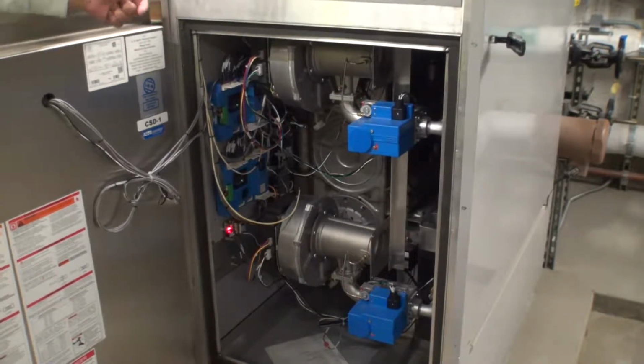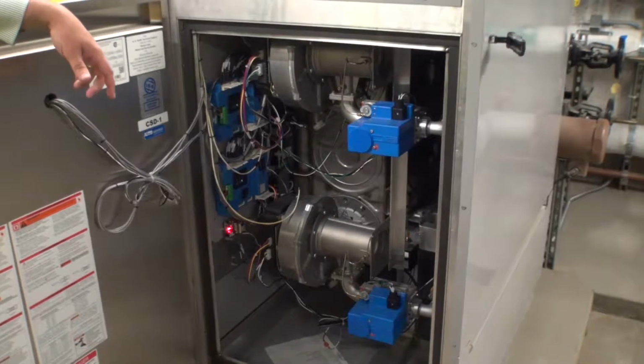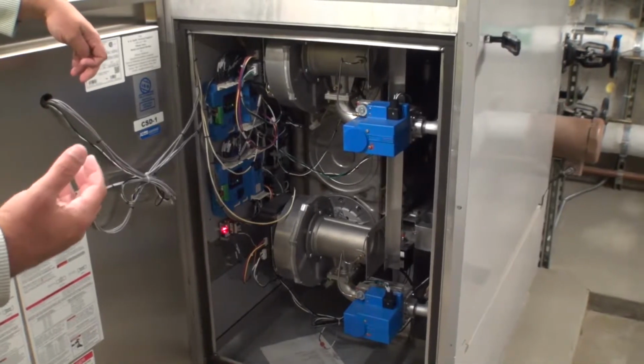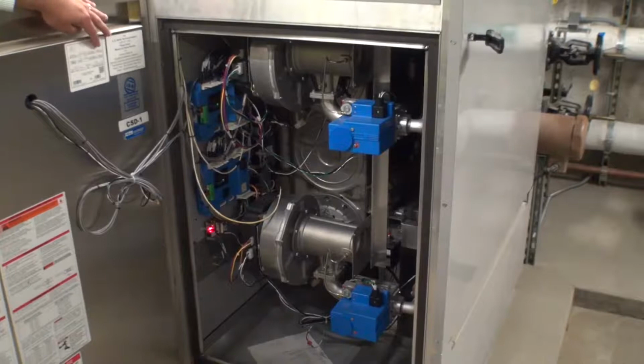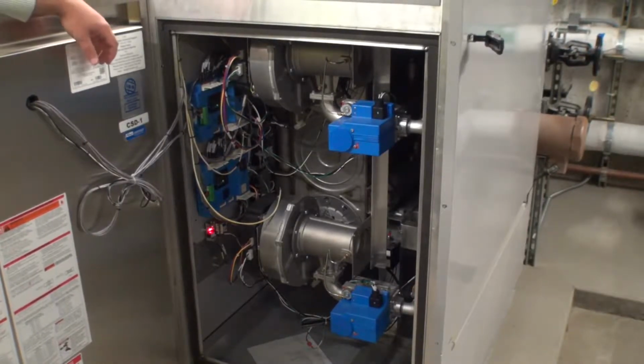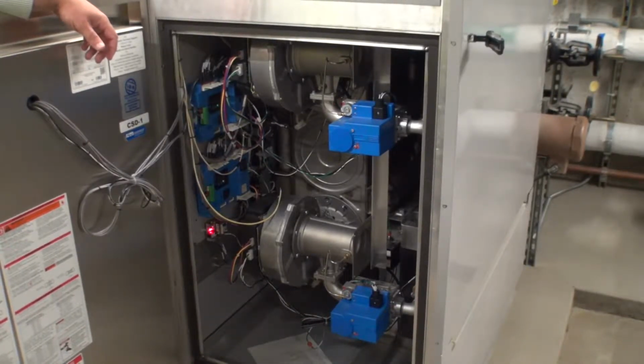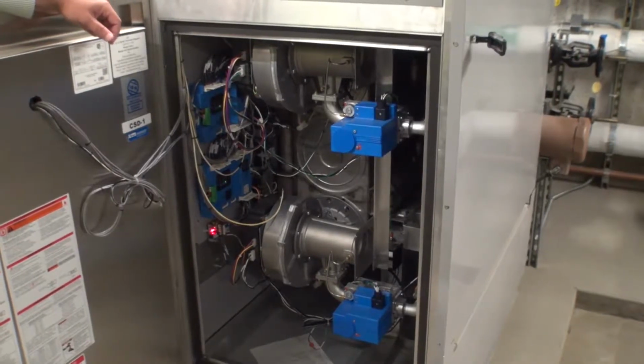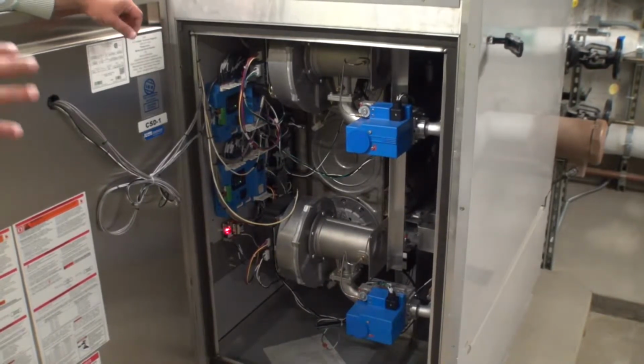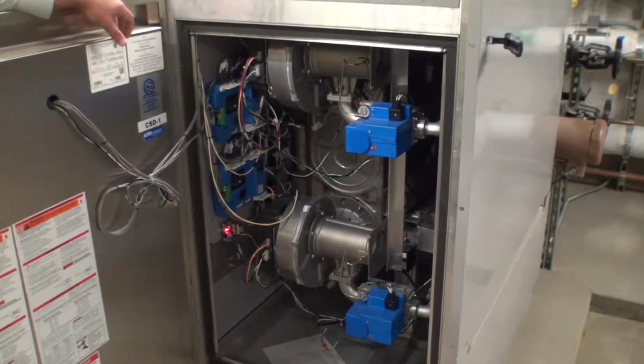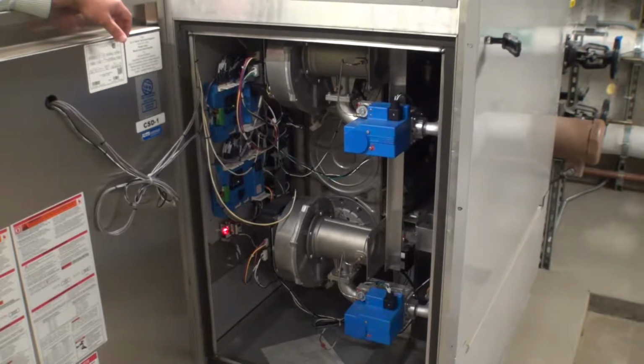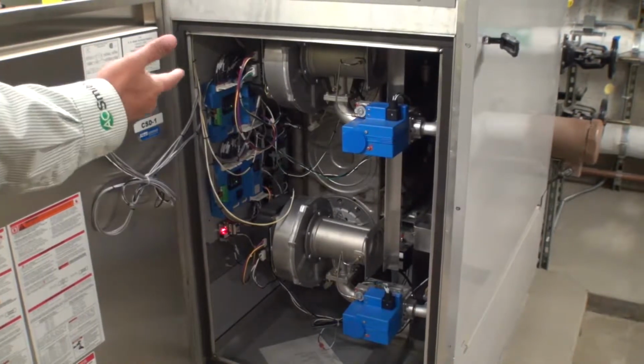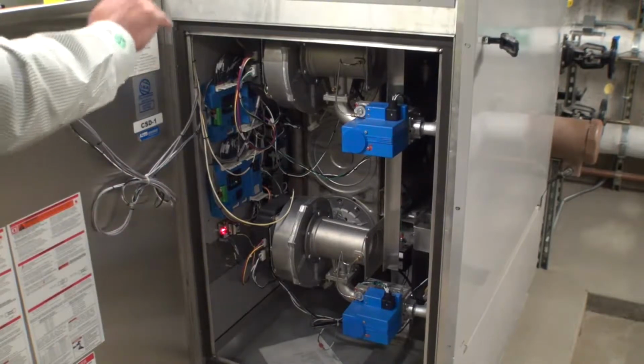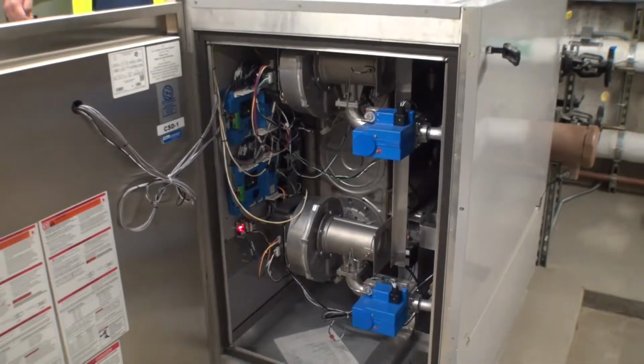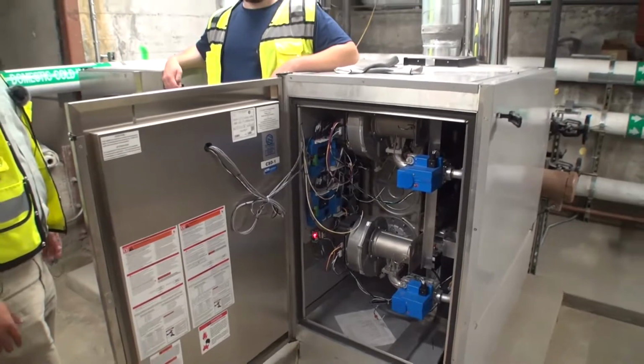Okay. The other thing to note on this equipment is it does have a 5-to-1 load rate, meaning that even though we're at 1.3 million BTUs, this thing's going to escalate in fifths to load. So it's going to start slow on that load, next level, next level, next level until full fire. So it's not all firing 1.3 million at once. It's going to have a staged start. With 2 units, that's actually a 10-to-1 then, because this one's going to stage, stage, stage, and that one's going to stage, stage, stage. So you actually have a 10-to-1 total fire ratio on these units.